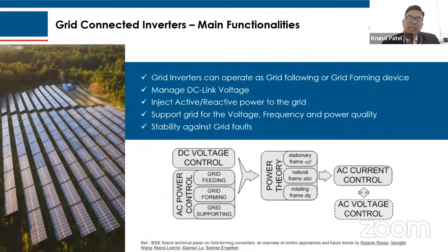If you look at the block diagram, there are the DC voltage control philosophies, then the AC power control philosophies, which are divided into grid feeding, grid forming, and grid supporting modes. Further, in the power theory, there are the stationary frame alpha-beta, which is required to maintain the output power angle connected directly to a grid, the natural frame ABC, and the rotating direct-quadrature frame control. These three power theories are utilized to maintain stability in voltage and frequency and to maintain good enough power quality for connection to the grid.